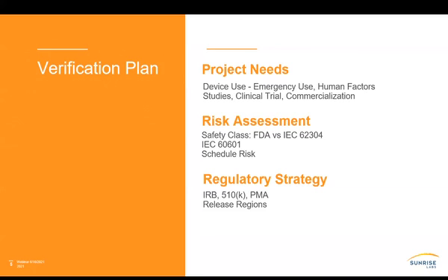your device under. So if you were to write that your essential performance is just equal to all of your essential requirements, then when you get into 60601 testing and your device gets hit with ESD and it maybe even shuts down or is irrecoverably damaged, right? It's no longer functional and it just shuts off. That may be a safe situation depending on what your device does. It might be better to shut off than to function not correctly.